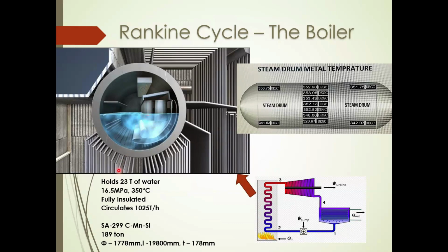Now, this 189 ton, 19 meters long, 17 centimeters thick pressure vessel holds about 23 tons of water during operation at a pressure of 16.5 megapascal, 165 bars, at a temperature of 350 degrees Celsius. Since the water inside the steam drum is at 350 degrees, the metal temperature of the steam drum is also at 350 degrees.